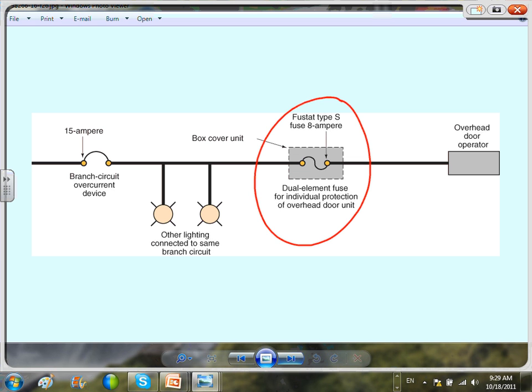It is a good idea. The reason for this is that the circuit breaker on the garage door, 15 amps, is not rated directly to protect your motor. So some manufacturers recommend a fuse right where they feed, a fused receptacle. They have the fuse right next to the receptacle, or a switched fuse outlet, where you need the switch because it's a motor, to disconnect it, and you need a fuse to protect it from overload and overcurrent. This is called a supplemental overcurrent protection device.